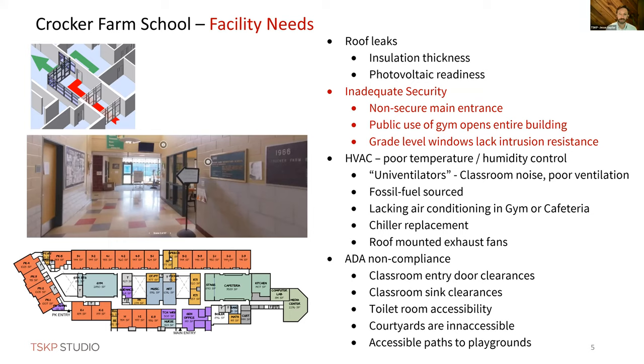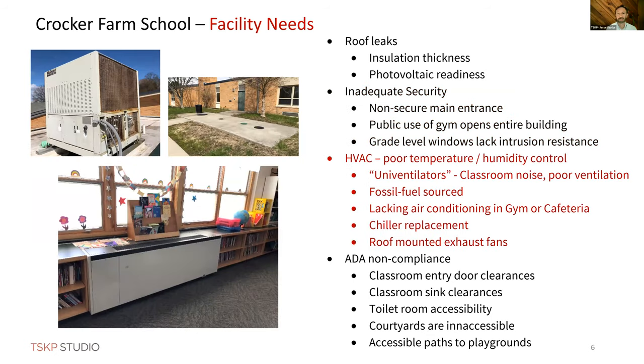Mechanical is always something we look at. The univentilators in the classrooms are in need of replacement. They're coming to the end of their serviceable lifetime, they're relatively loud, and they don't handle moisture control well. As they get to the end of their life, the dampers start to get stuck, so their purpose to bring in fresh air starts to be compromised. We recommend replacing them with an electric split type system.